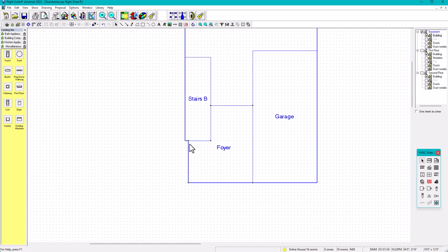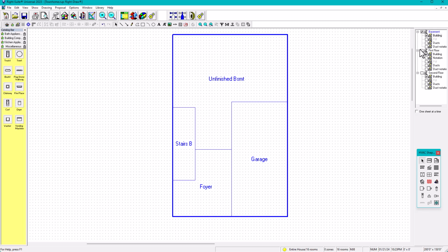And the reason is, at times, when we're doing heat load calculations, we are not accounting for the thickness of the wall. As you can see, these are just lines, but the walls actually have thickness. So usually when that happens, I'd rather make it bigger than smaller, when we're accounting for worst case scenario, right? Okay, so now it's a little bit lining up.